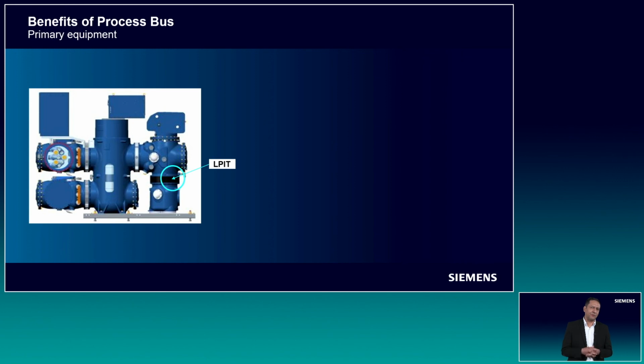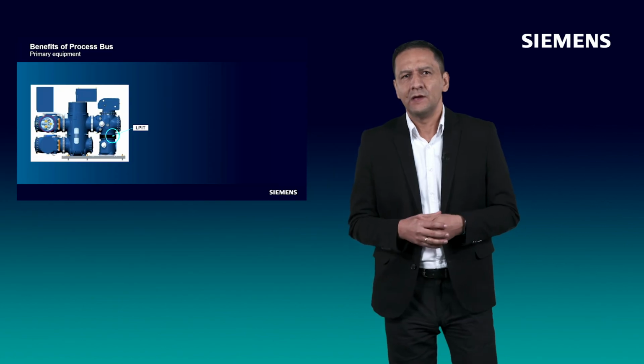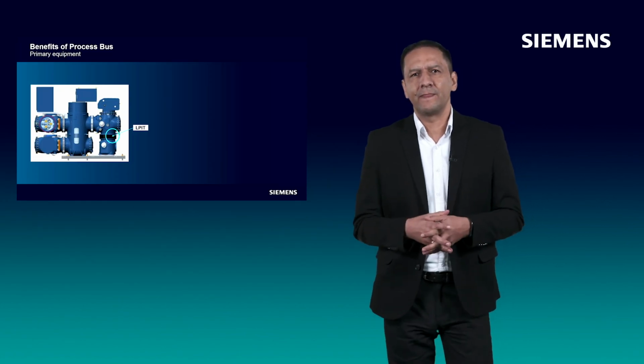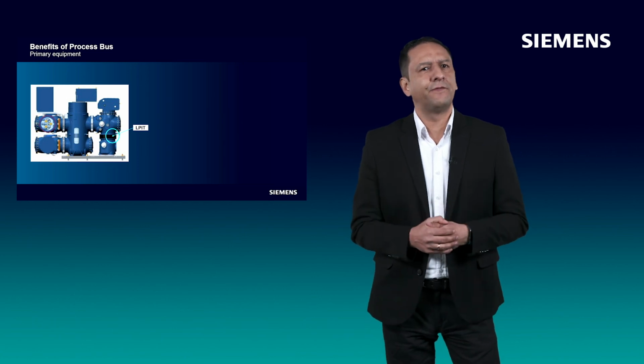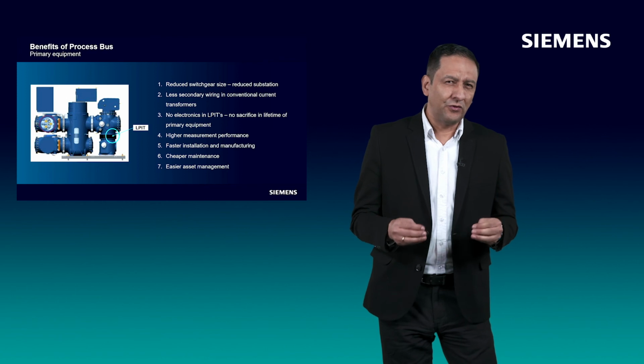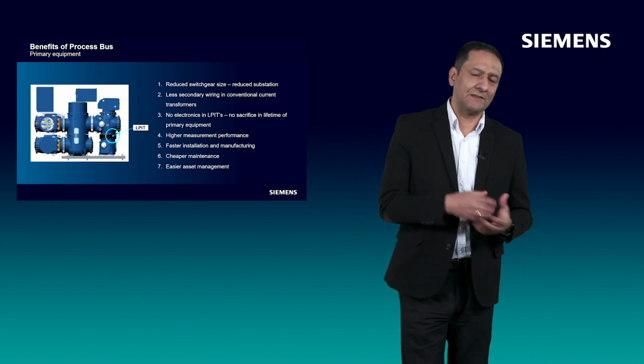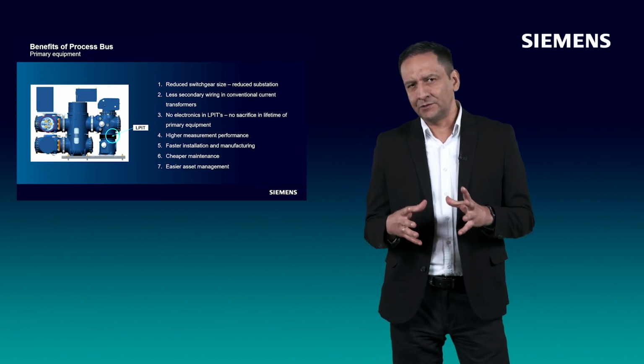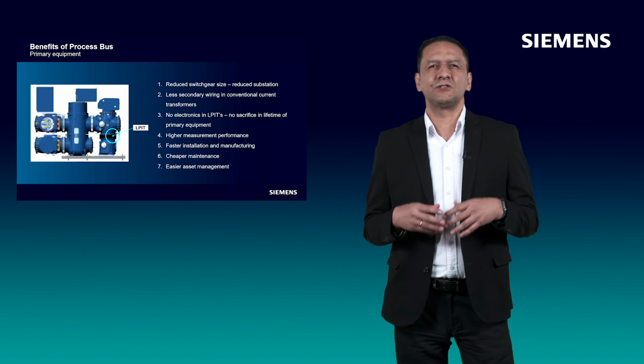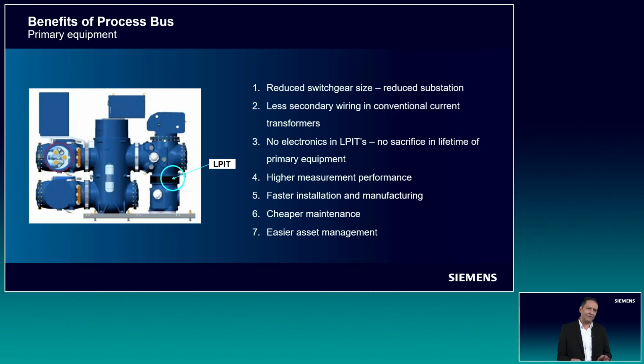Let's take a look at primary equipment, and which benefits process bus technology could bring. Of course, it will allow smaller primary equipment, especially in high voltage gas insulated switchgear, which we call GIS, by using low power instrument transformers, LPITs. We can dramatically reduce their size and weight. Additionally, we will achieve higher measurement performance. With process bus technology, we don't need as many secondary windings in current transformers as before. It means that we can manufacture high voltage equipment faster and build substations faster. Additionally, by having different sensors in primary equipment, we can make asset management easier.